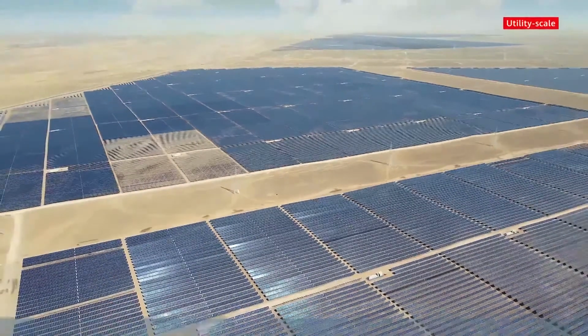For the industry, the two main challenges of the energy storage system are battery power loss due to mismatch of the cells, and potential hazards such as fire and explosion caused by external forces, high temperature, and abnormal battery operation, such as overcharging and over-discharging. And the Huawei energy storage solution is an intelligent string-based solution. As we mentioned in the previous topic, the maximum charge and discharge capacity is improved by 15% through one pack optimization and one rack management.